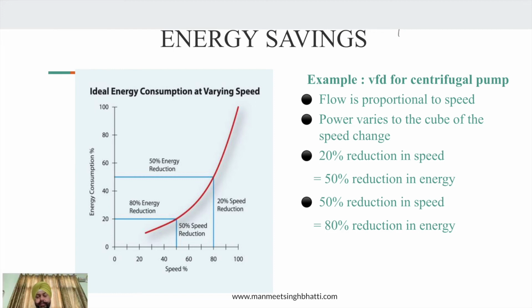Now, as you can see, there is a basic example, and this is a basic chart that we have shown of how it is going to work. If you see on the left side of the chart, it is the energy consumption. We have energy consumption of 100%, and a speed of 100%. If the speed is at 100%, you have energy consumption of 100%. But if you reduce the speed by 20%, say if you have a 100 rpm motor, you reach a speed of 80 rpm, you actually reduce your energy consumption by 50%. Now I'm talking about the energy consumption of electricity.